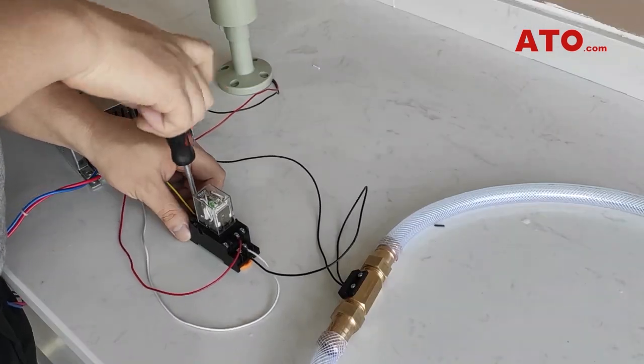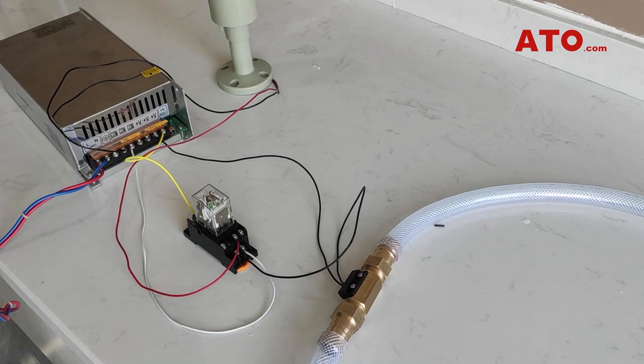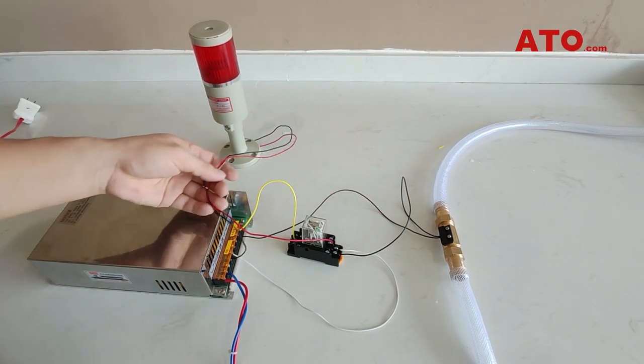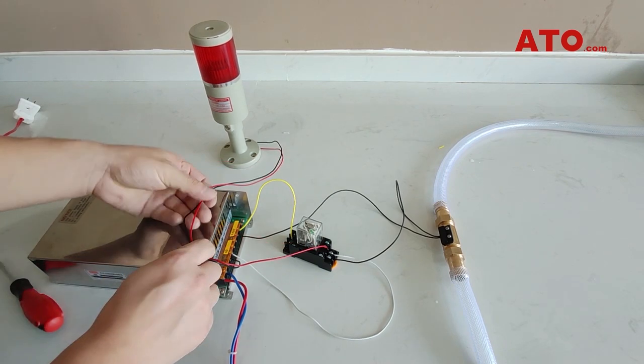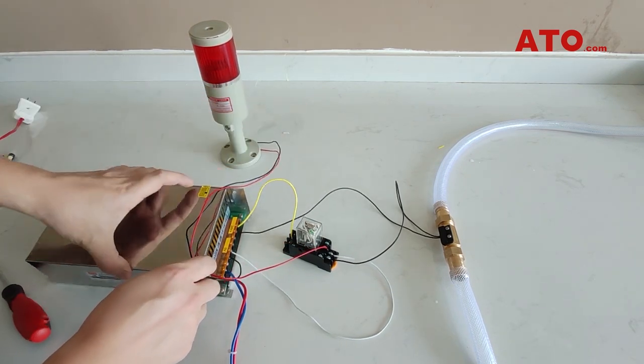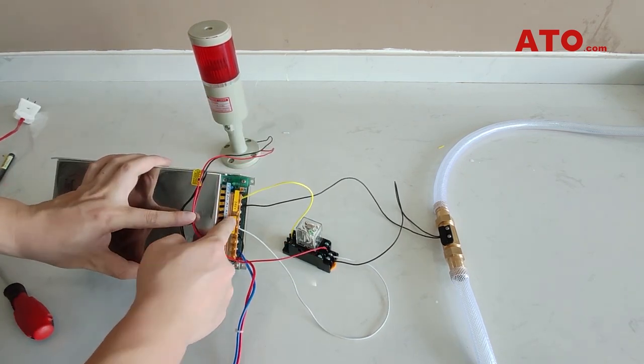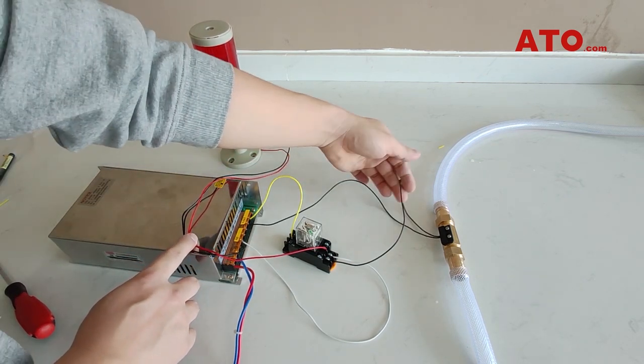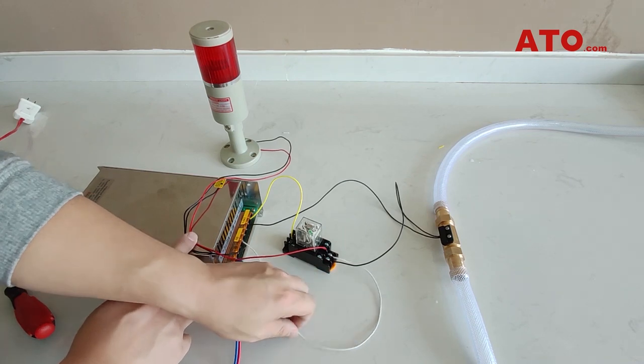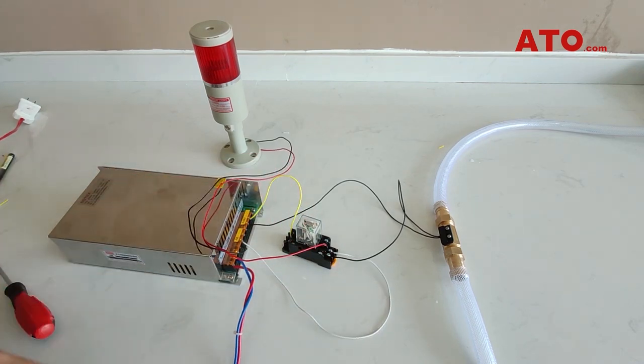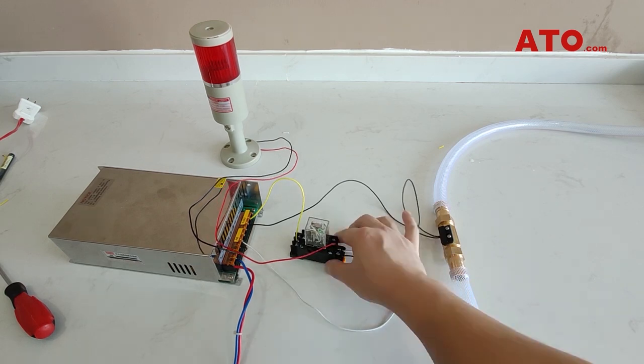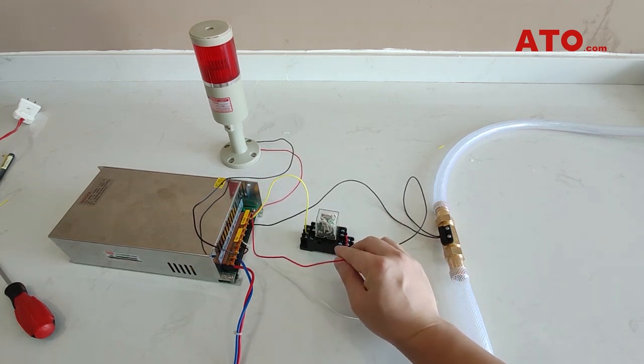Add the warning light to the circuit. As shown in the demo, connect one end of the magnetic water flow switch to the positive pole of the DC power supply, and connect the other end to the positive terminal of the relay coil. Then join the coil's negative terminal to the COM port of the supply. The warning light is controlled by the normally closed contacts of the relay.